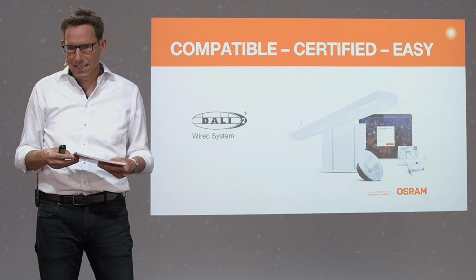So let me quickly summarize. The DALI system is not a revolution, but for sure it's an evolution. We have a very nice and comprehensive portfolio of luminaires, control devices, and sensors, everything based on the DALI 2 standard. We have a new way of commissioning, drag and drop, everything browser-based, high level of flexibility, and we combine lighting control with IoT, which gives a lot of potential for the future. Keep in mind, what you install now should be there for the next 10 to 15 years, but these devices are so future-proof that developments we see in the near and mid future can be upgraded to the controller.